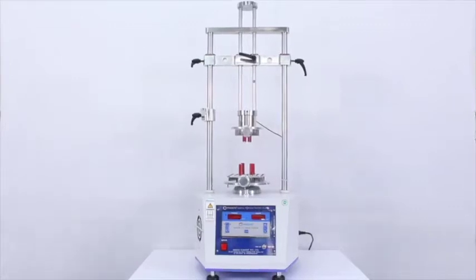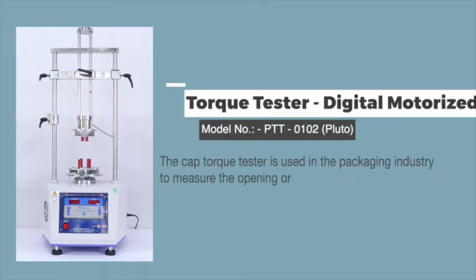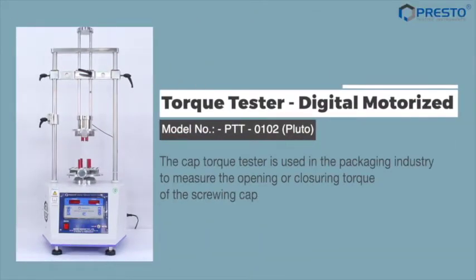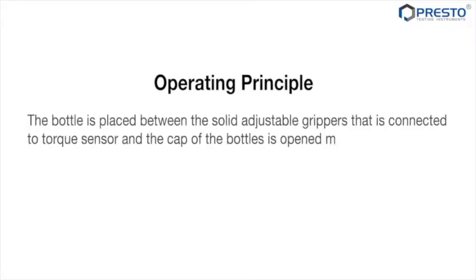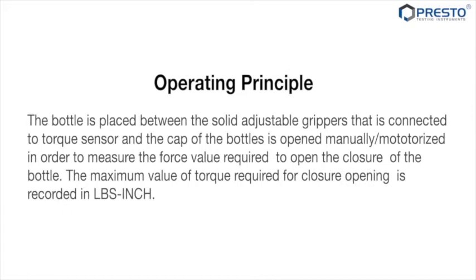Torque tester. Torque tester is used for measuring the torque required to open the cap of bottles. Operating principle. The bottle is placed between the solid adjustable grippers that is connected to a torque sensor, and the cap of the bottle is opened manually or motorized in order to measure the force value required to open the closure of the bottle. The maximum value of torque required for closure opening is recorded in lb inch.